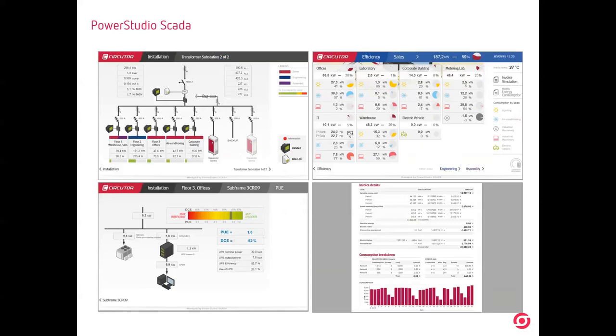And here you can see some screens from the software. With an EMS software, we can see the consumption, the different uses, the different zones, but we can also create diagrams, like you see. It's a SCADA screen with diagrams, with our devices, with the protections, with the consumptions. Also, we can calculate the effectiveness of the electronic devices that we have in our installations. And below on the right side, you will see an invoice. We are receiving automatically at the end of the month invoices telling how much energy we have consumed, if we have any penalty in reactive or in maximum demand, and we know before receiving the official bill from the utility.